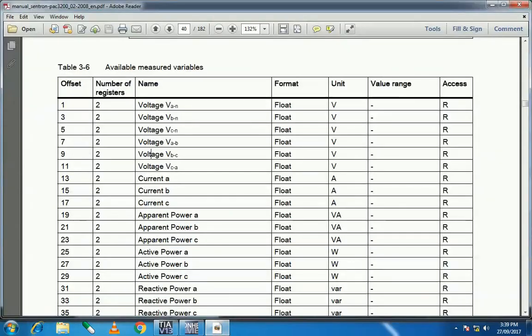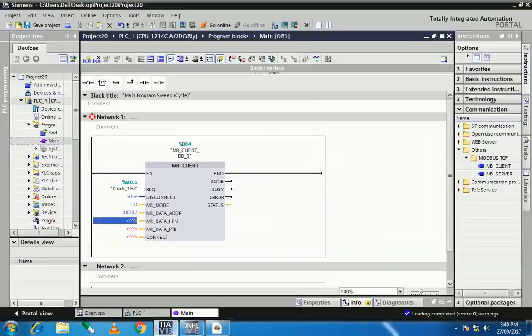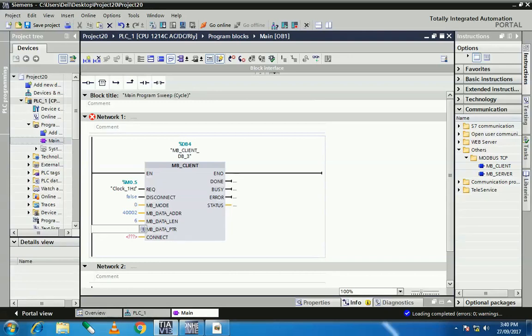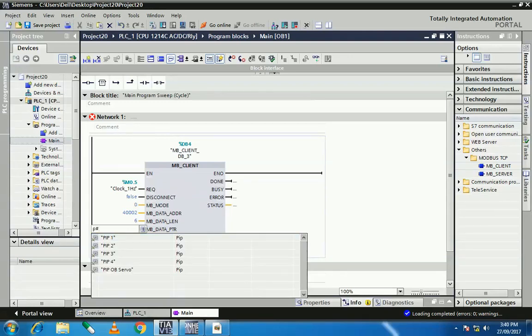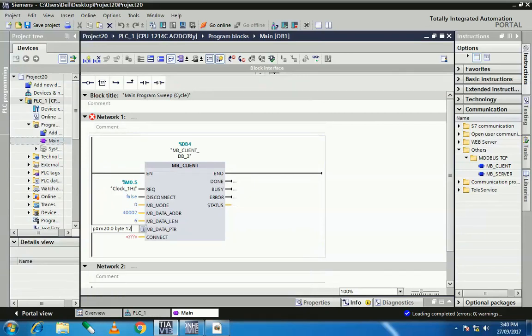For data length, I am reading three variables, so I need a total of six registers — two registers per variable, times three variables equals six. So I set the length to six. MB_DATA_PTR means Modbus data pointer — the memory in the PLC where the data read from the energy meter will be stored. Here I assign memory pointer M20.0, byte, and six words, which is a total of 12 bytes.